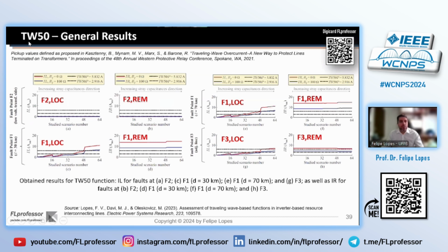Considering the overcurrent element, it is possible to conclude that for measurements on the remote side, on the grid side, they are very well behaved. But for measurements taken on the IBR side, the presence of stray capacitances will dictate the sensitivity of this function. So only for higher stray capacitances will we see the quantities exceeding the thresholds and guaranteeing their operation.